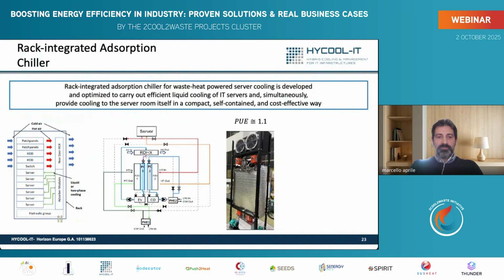So basically, we are working on a compact, self-contained, and cost-effective way to provide cooling. However, this is not easy to achieve. The design of the adsorption chiller had to be completely changed from the usual way because of space constraints. What you see on the right is an example of a proof of concept showing how compact the machine is, and this can clearly be installed in the back of a rack.